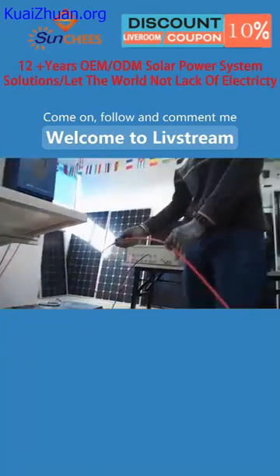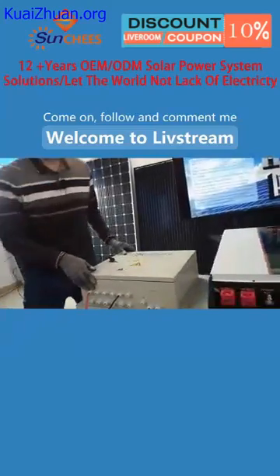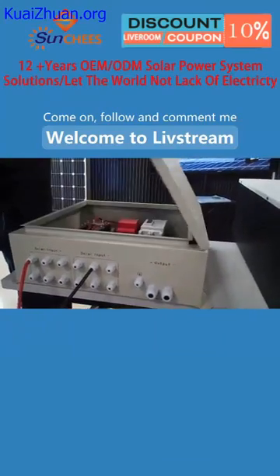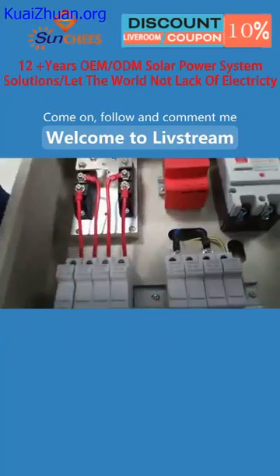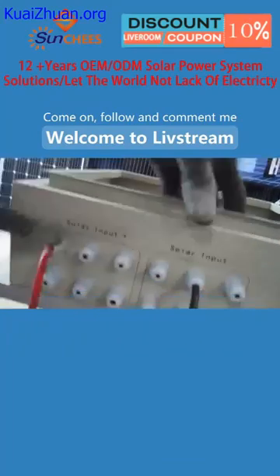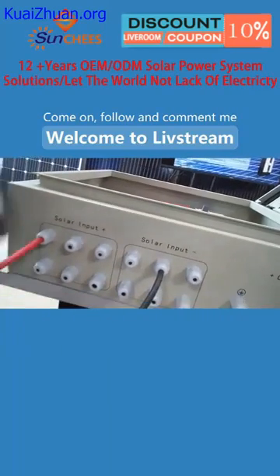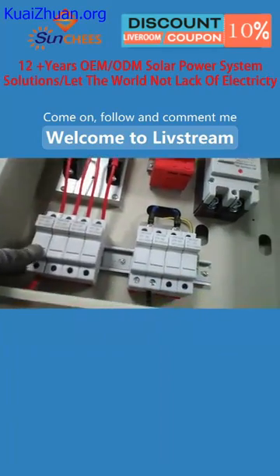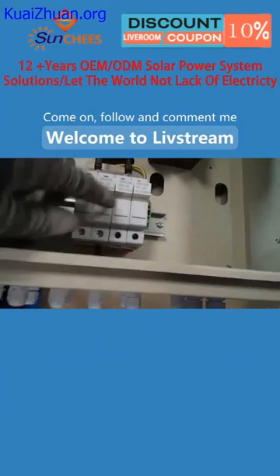cable and black PV cable to our PV combiner. As I told you, our PV combiner's function is to simplify the wiring between the PV array and hybrid inverter. So next step, we'll connect the PV cable into our PV combiner. This side is solar input positive, and the right side will be solar input negative output port. So the red cable connects to this one, positive input, connect to the breaker with fuse. And then the black one will be connected to the negative side.